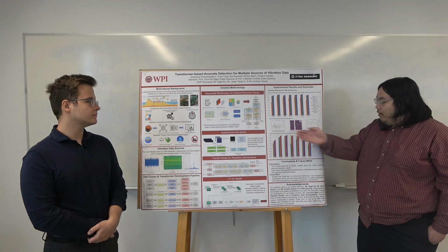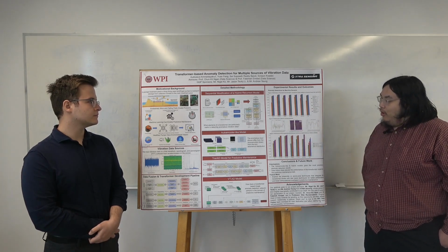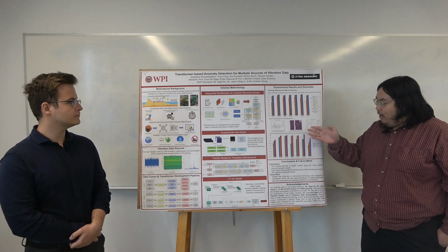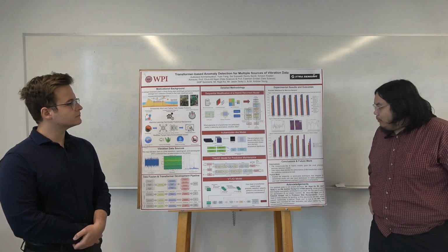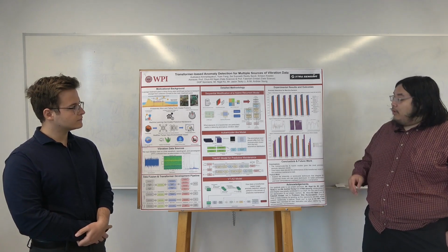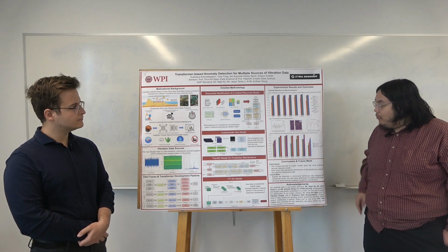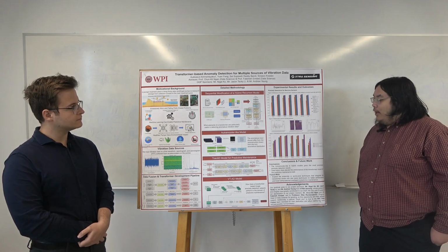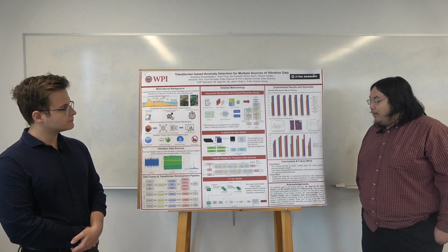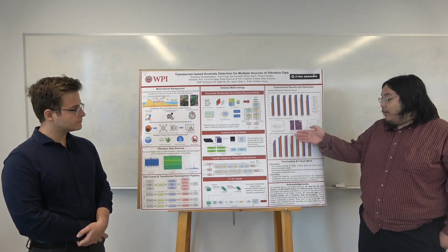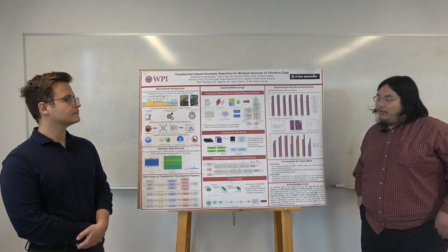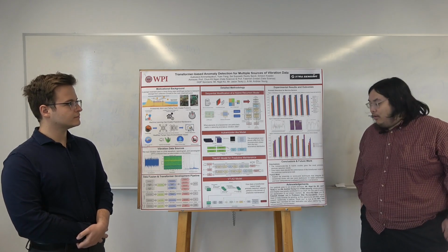We can see that the model correctly classifies this operation as normal, and when we look at this one where the sensor is supposed to be under the faulty condition, we can see that, as denoted by purple, the model correctly classifies the part that is anomalous, but also gives us insight on some parts that might look not anomalous from the signal perspective.